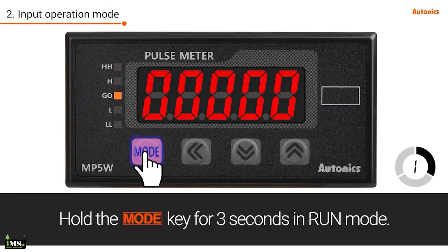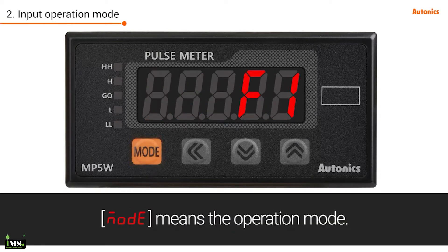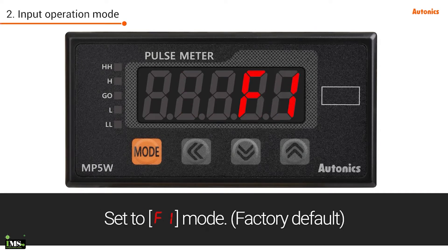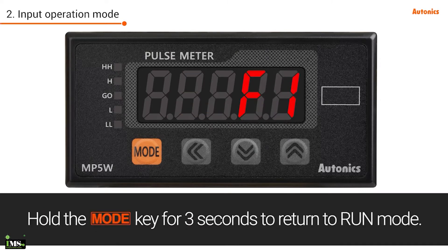Hold the mode key for 3 seconds in run mode, then press the mode key. Mode refers to the operation mode. Set to F1 mode. F1 mode is for measuring frequency, revolution, and speed. Hold the mode key for 3 seconds to return to run mode.